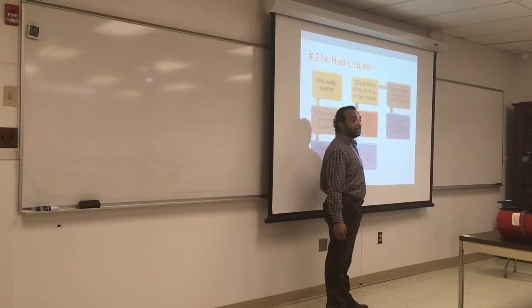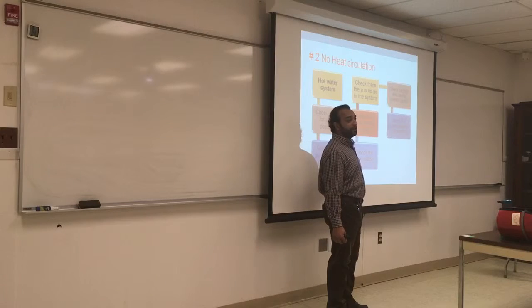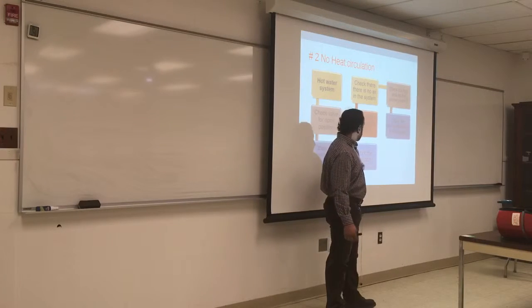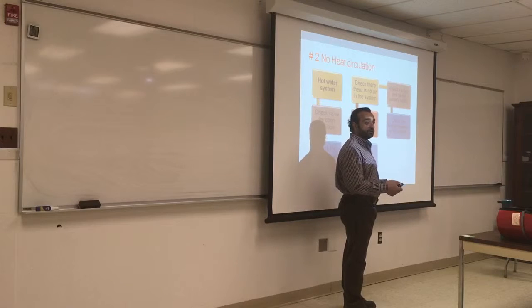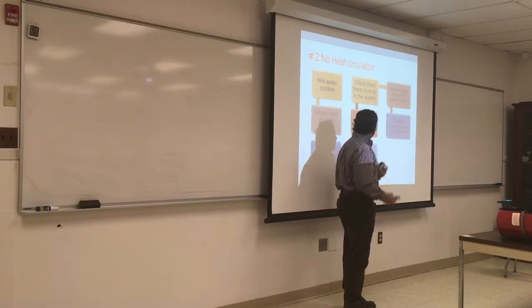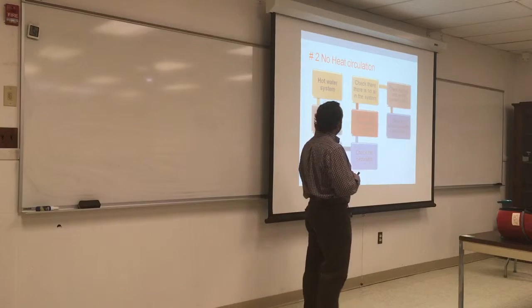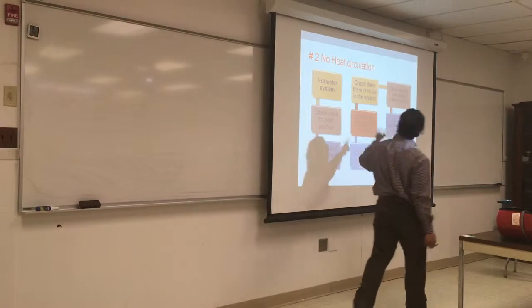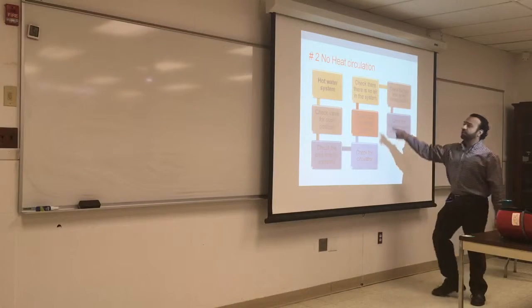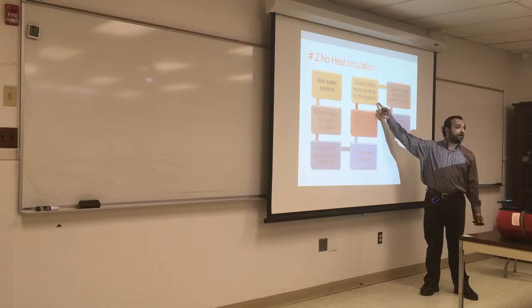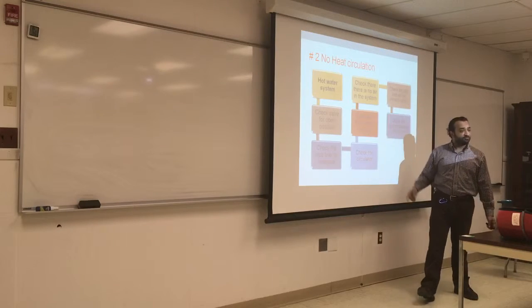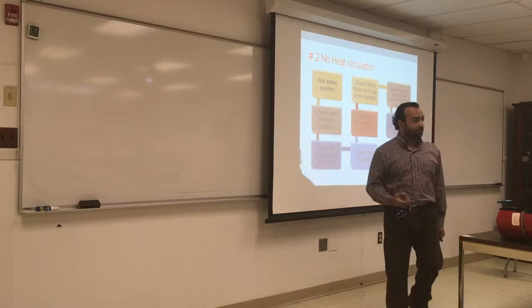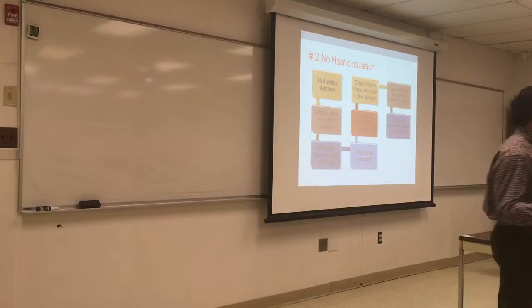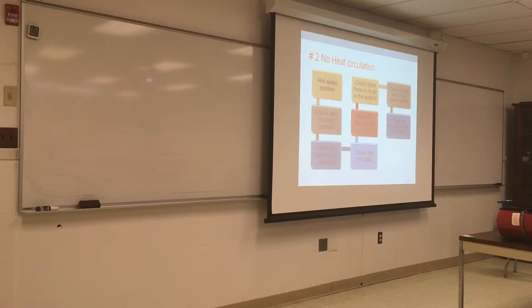Purge it. There's always going to be a purge and makeup line in the boiler. So check the circulator. Make sure it's getting enough voltage. It is circulating. Check the flow control valve. Check there is no air in the system. If there's air, the system's going to be airbound. This happens a lot more than you think. If there's bubbles in the system, it's not going to circulate. Whenever you change oil or line, if there's some bubbles, it's going to impede the progress of flow.